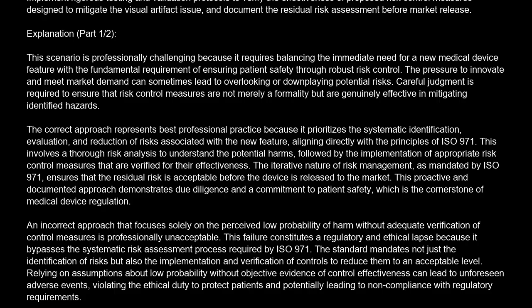This proactive and documented approach demonstrates due diligence and a commitment to patient safety, which is the cornerstone of medical device regulation. An incorrect approach that focuses solely on the perceived low probability of harm without adequate verification of control measures is professionally unacceptable. This failure constitutes a regulatory and ethical lapse because it bypasses the systematic risk assessment process required by ISO 14971. The standard mandates not just the identification of risks, but also the implementation and verification of controls to reduce them to an acceptable level. Relying on assumptions about low probability without objective evidence of control effectiveness can lead to unforeseen adverse events, violating the ethical duty to protect patients and potentially leading to non-compliance with regulatory requirements.